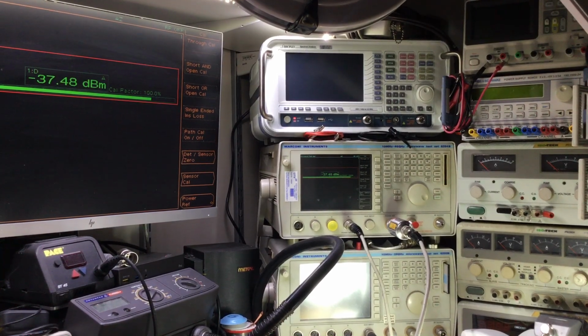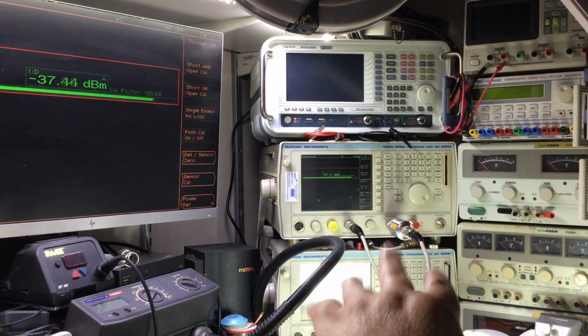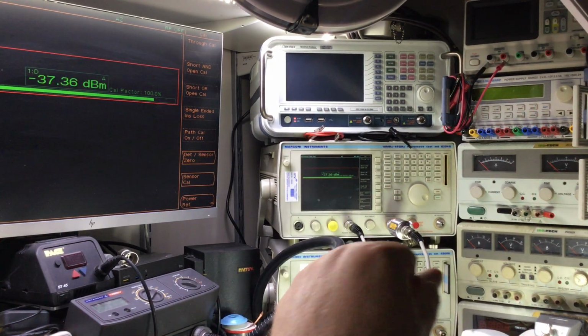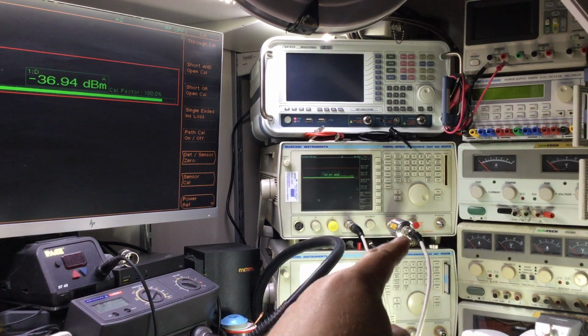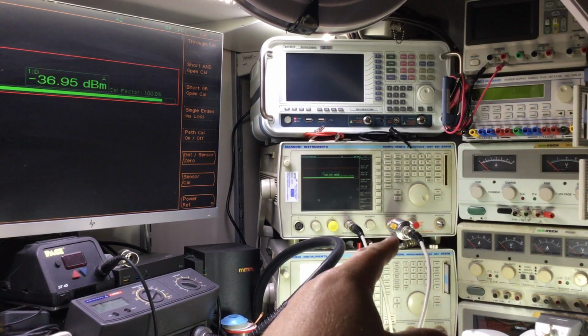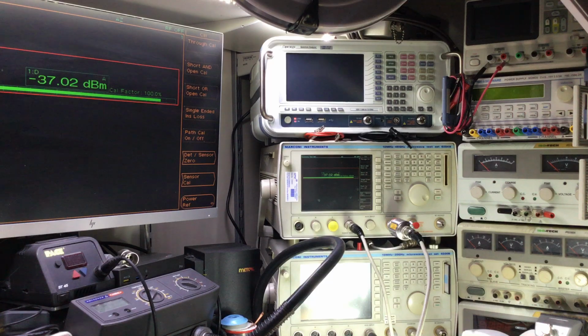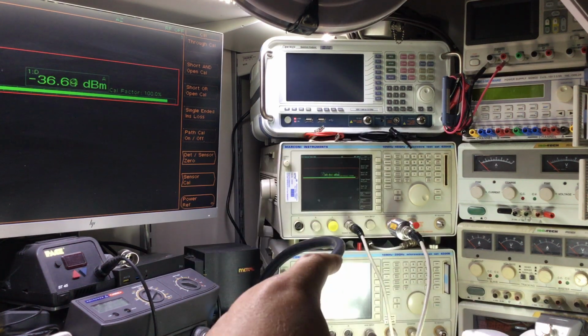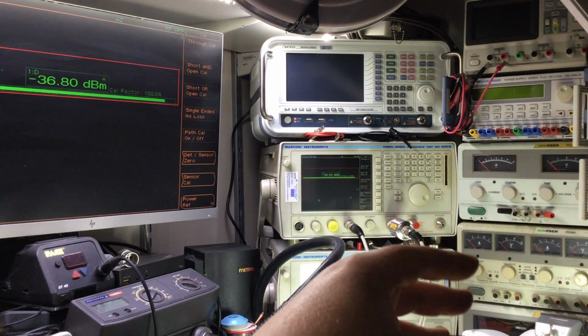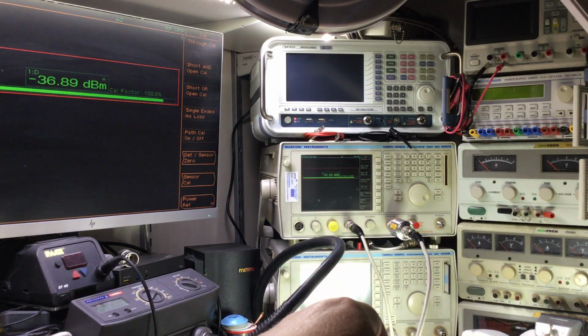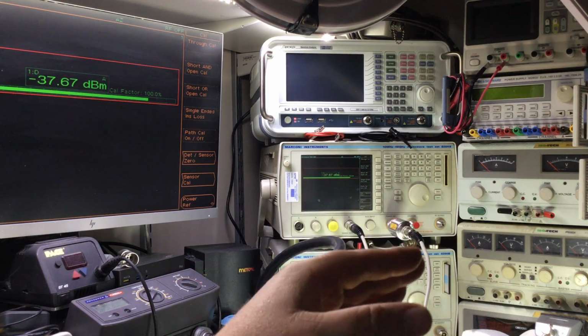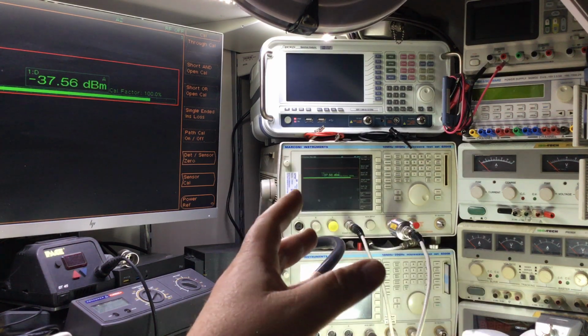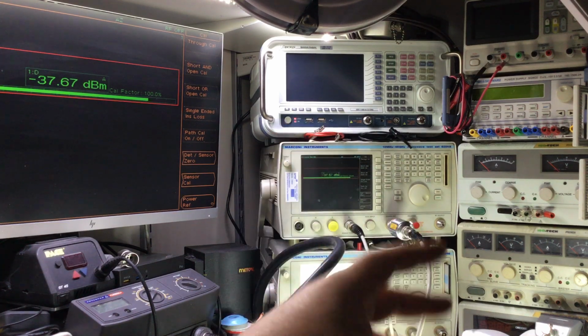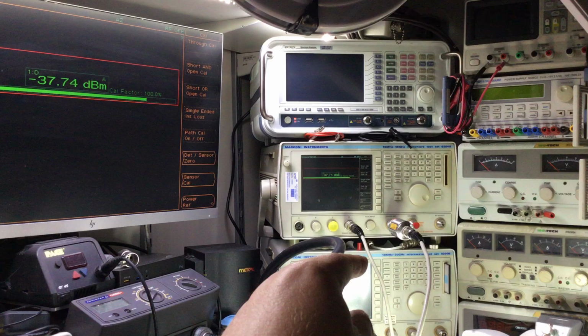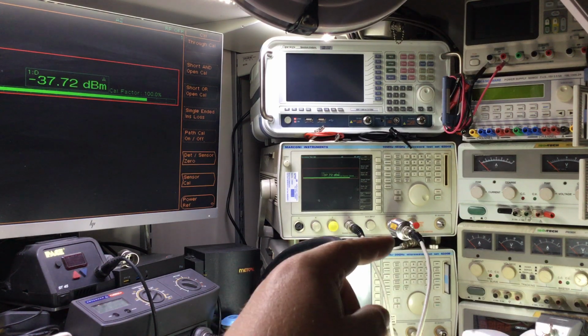Okay, so just to explain what's going on here, we've got the Marconi microwave test set up. After a long time, when you've entered all the calibration factor, linearity factor, all the frequency table, as per the sensor calibration data which accompanies the sensor, then essentially you set the sensor up in the Marconi microwave test set to measure correctly, because without that linearity data, cal factor and all the frequency tables representing all the response, then the sensor wouldn't read properly.